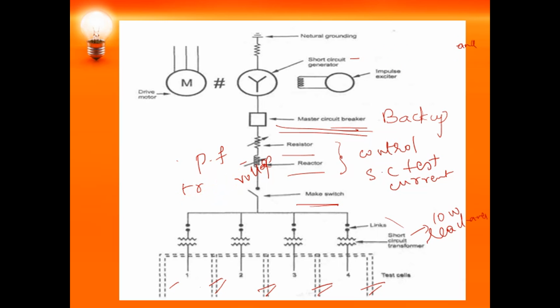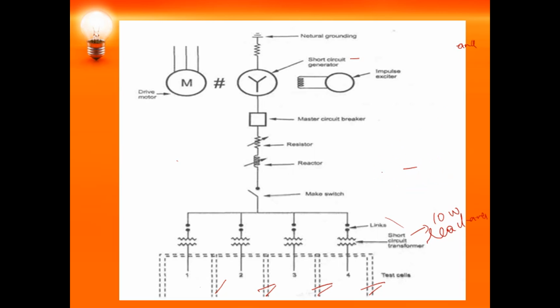Just have a look here. First, what should happen? We have a motor. That motor has to drive the generator, and once it has attained a certain speed, you switch off the motor. Second step is you have to switch on the impulse exciter. Next, what has to be done? See to it that the master circuit breaker contact is in the closed position. Then, in case you have any observing or metering system, you have to switch that on. After that, you are going to apply the short circuit current to the circuit breaker which is under test.